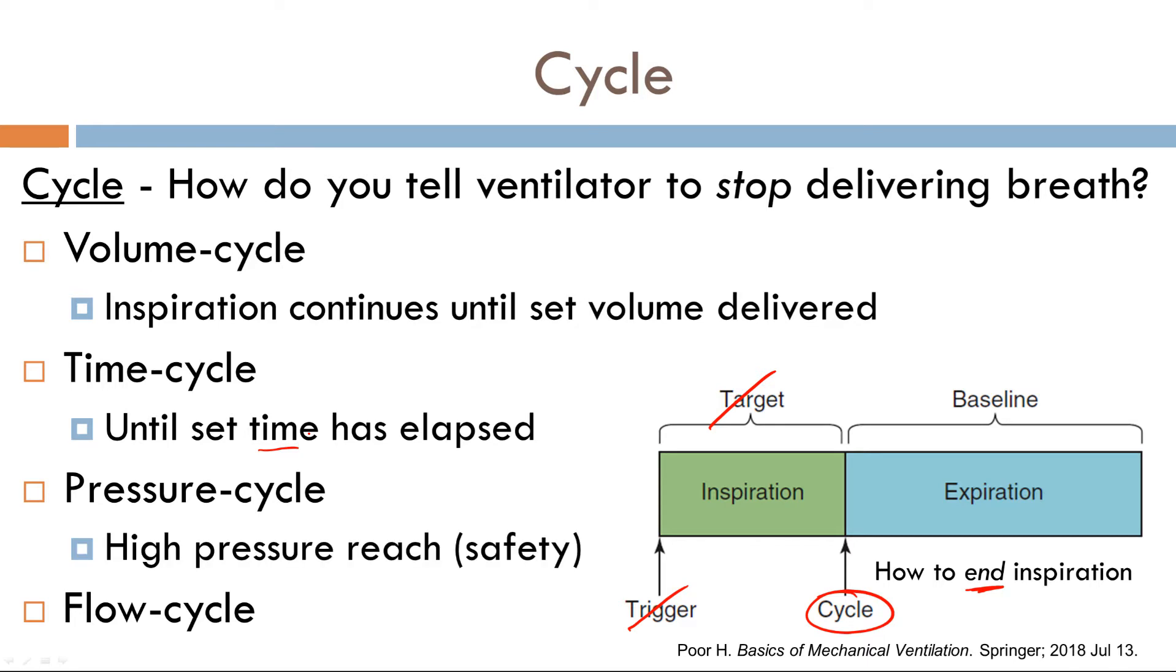What about pressure cycle? In pressure cycle, you set a pressure cycle, which is usually a backup safety mechanism. Once the pressure exceeds 60 centimeters of water, boom, stops delivering a breath. Why continue to deliver a breath if the pressure is exceeding so high above 60? So as a safety mechanism, you use that to save yourself from possible barotrauma.